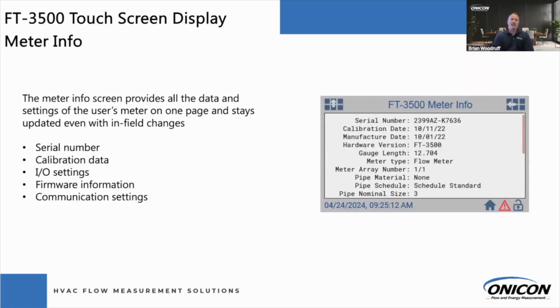Next, meter info. This is really important. If you ever call ONICON, one of the first questions you're going to be asked is the serial number. Well, a lot of times that hanging ID tag that accompanies the meters can be lost. They can be cut off, like it's not needed. Or imagine the meter is 30, 40 feet in the air and you're not able to see that information. So having that remote display at eye level, you can quickly go through the touchscreen display and see all of the meter info data. And that's to see the serial number, calibration information, and then knowing, as Mike mentioned, that 3-year warranty or that 1-year no fault, you can quickly go back to the display and see if you're still within that time frame. Plus, you're able to check any type of configuration of the inputs and outputs available for that flow meter.